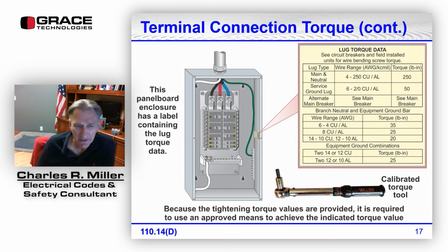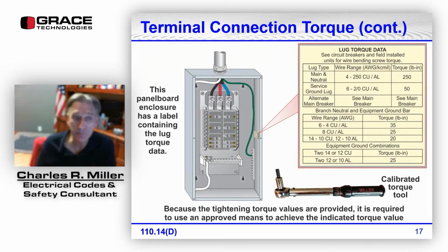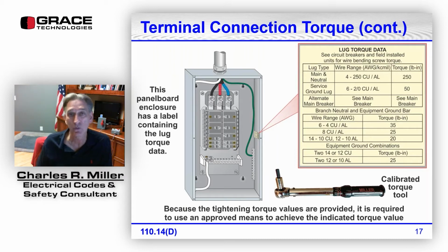All right, so here is an illustration, and it may be kind of hard to see the type of panelboard this is. This is a Square M. I know you've heard of Square D, but this is a Square M, the Charles R. Miller brand panelboard. This panelboard has a label containing the lug torque data, and they've had this data in panelboards forever. In fact, it wasn't specifically stated in the code book until fairly recently, but there are other provisions that said, for one thing, where we started out a little while ago, that equipment has to be used and installed in accordance with the installation instructions. Well, if the installation instructions give you the torque data, then we were supposed to go by that for years and years.